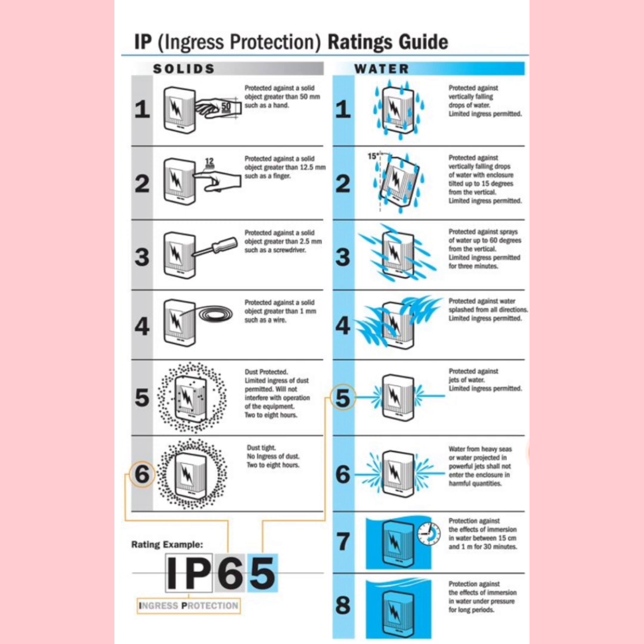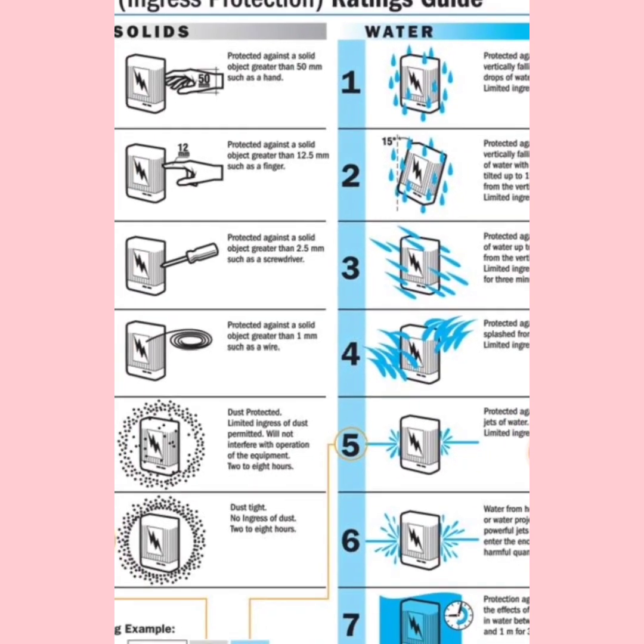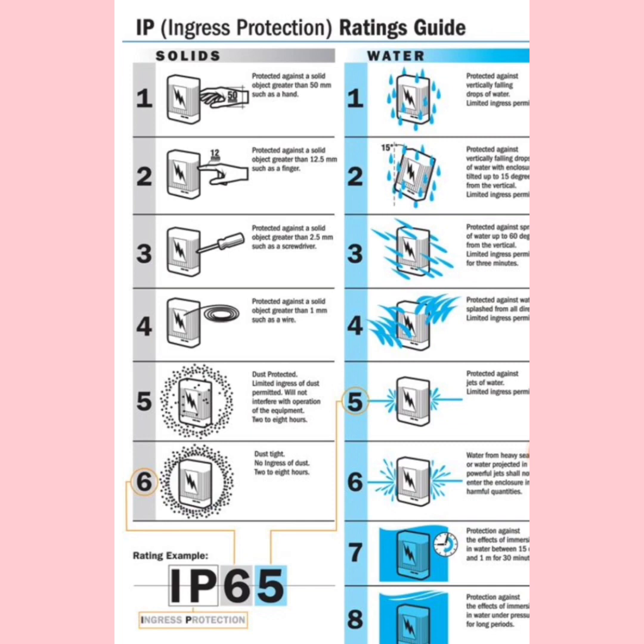Looking at solid protection, the very first number talks about protection against objects having size more than 50 mm — that means protection against your hand. The second number gives protection against objects more than 12.5 mm. For number three it is 2.5 mm, and for number four it is 1 mm. So 12.5 mm means a finger, and 2.5 mm means a screwdriver.